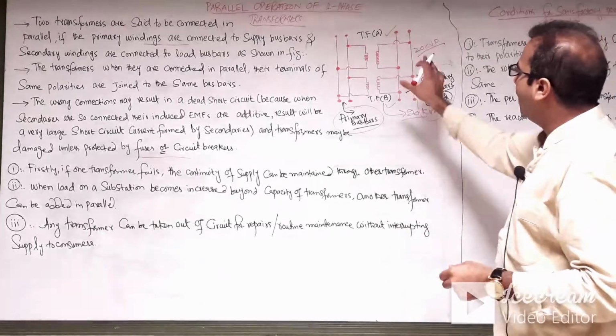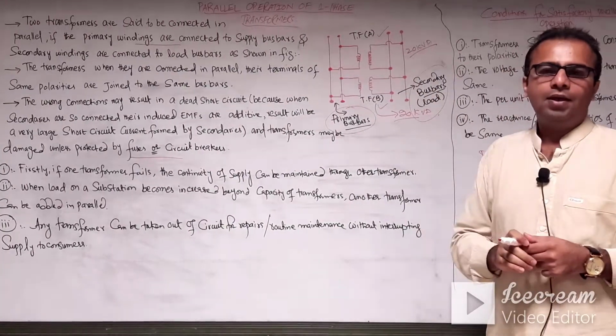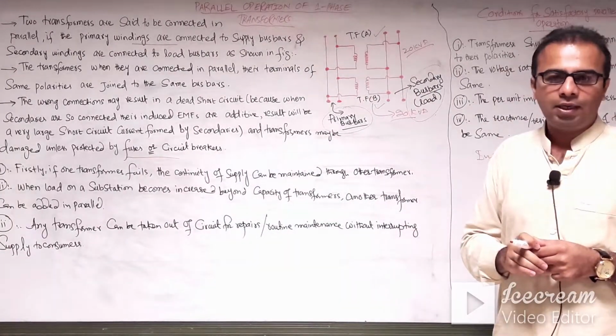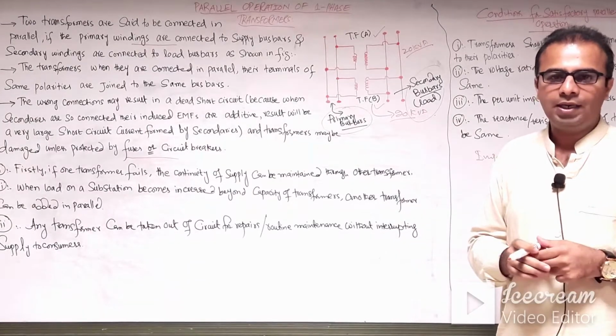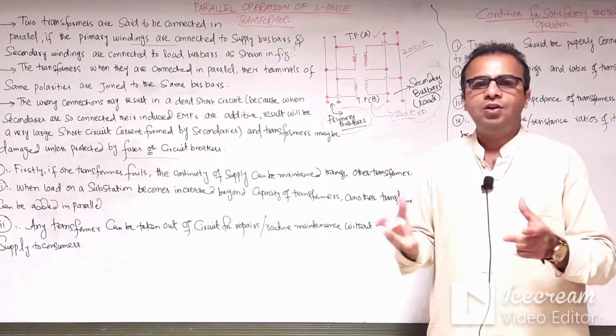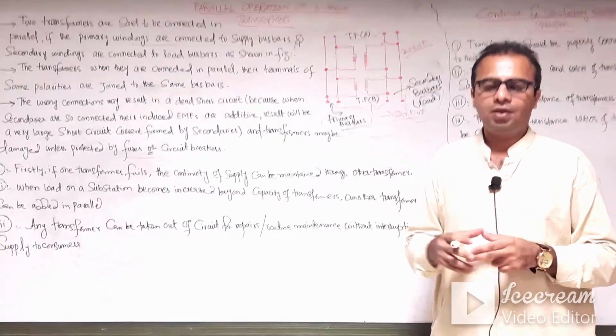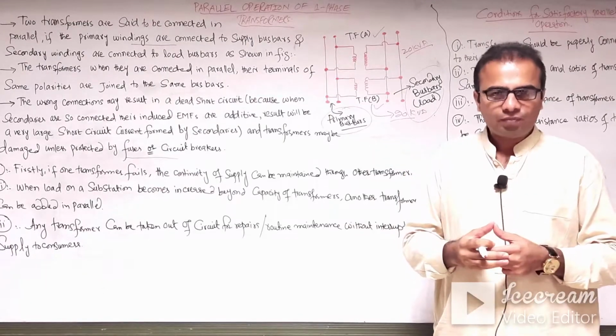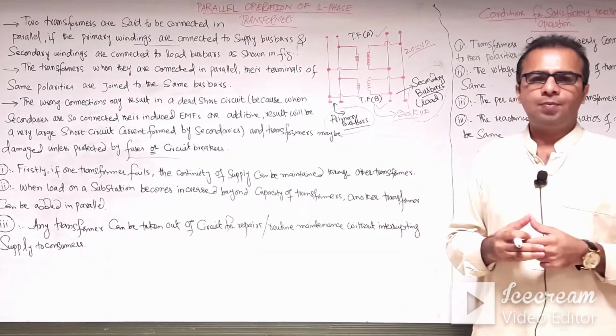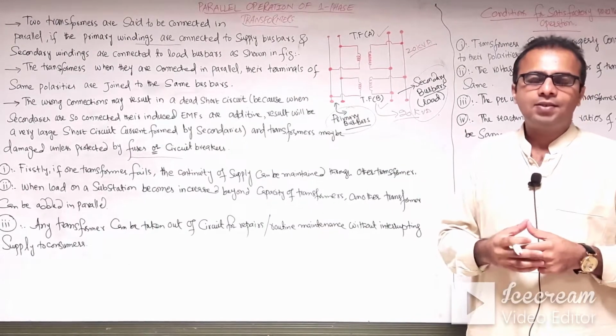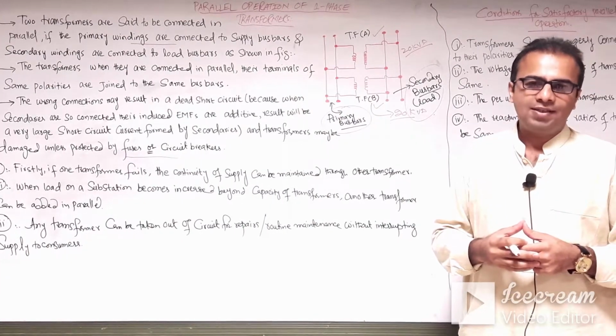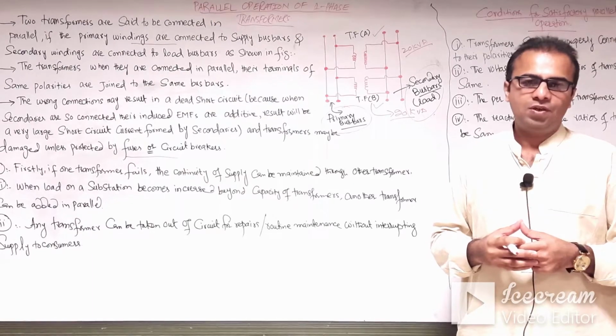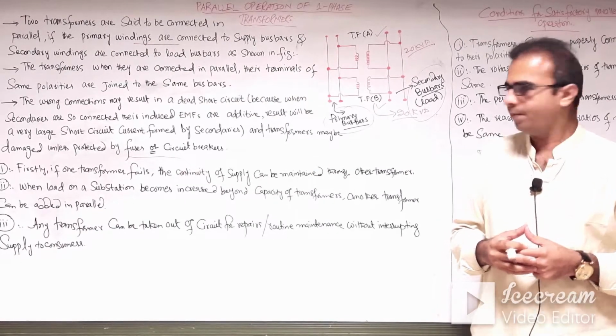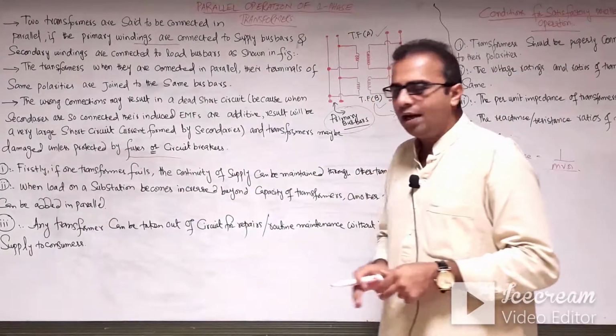Now if the transformers are connected in the wrong connections, or in the additive polarity, the result will be additive induced EMFs, and additive polarity is not considerable. So we always consider the subtractive polarity or the same polarities in the parallel operation of transformers for satisfactory operation. So what are the advantages?